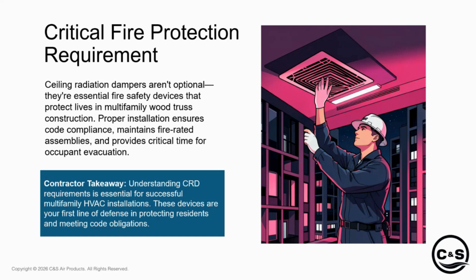All our CRDs are rated with the assembly, with all the different requirements included. If you take out one critical piece, say the ceiling radiation damper, you don't know how that's going to react. And especially with different testing agencies, you don't know how strict they are with these tests. That's why we typically push the UL side of things, saying hey, we're fully rated with UL, fully listed, and we try not to go outside the bounds too much with different testing agencies.